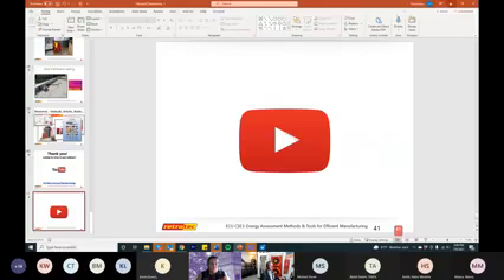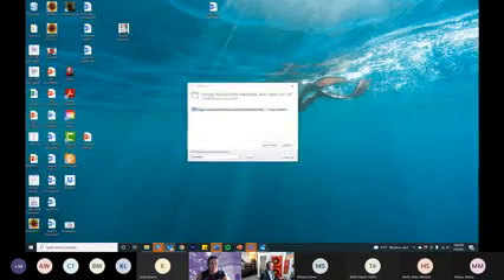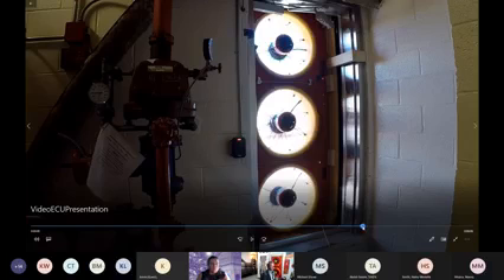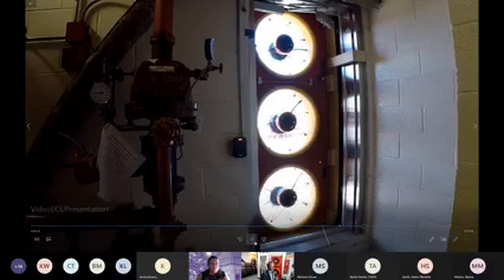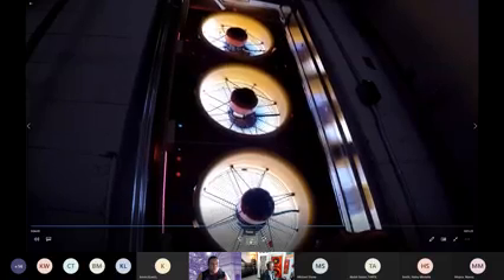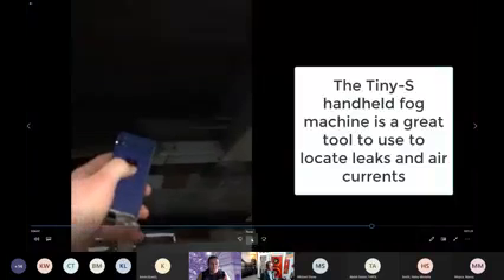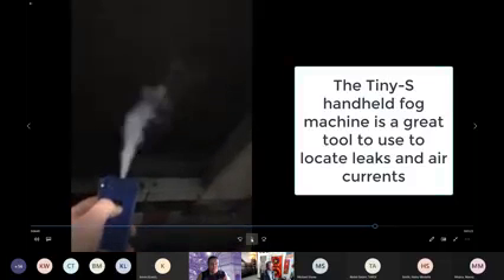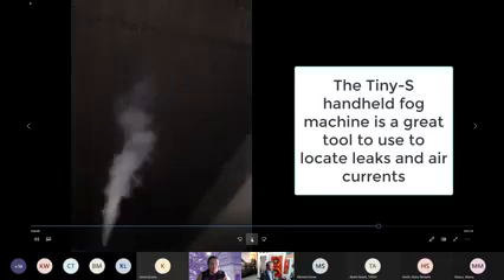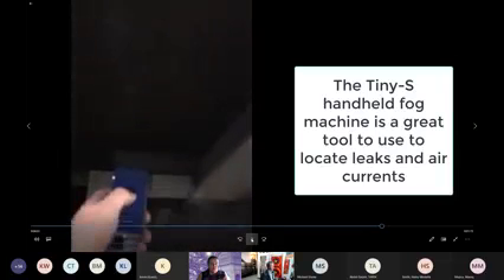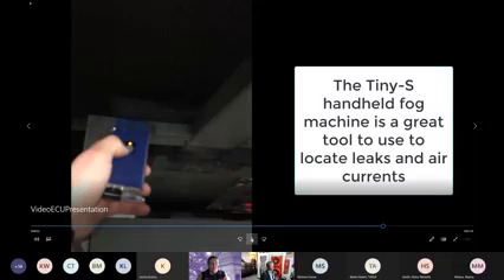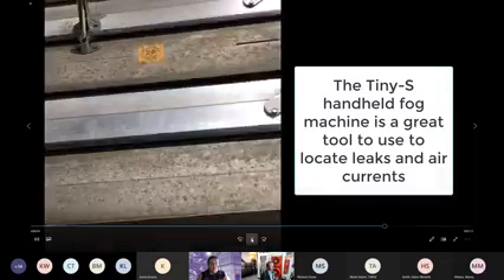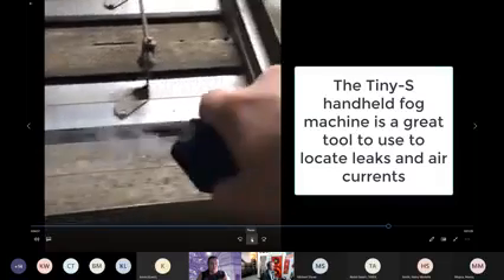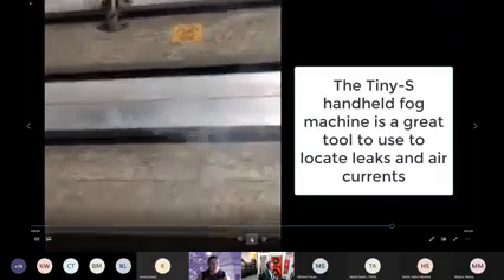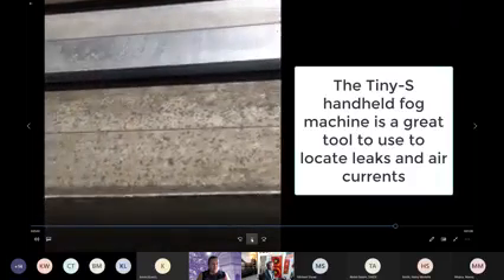And while I still have just a couple of minutes left here, one thing that I'll show you is just what some of this looks like. If we're running fans, this was in an actual building in New York City where we used about 33 of these fans. They were having energy problems and really couldn't afford the utility bills out of their budget. And so we went and tested it. And so using that fog machine, we can see where a lot of these leaks were occurring. At the top of the building, there were all of these louvers up there in the elevator penthouse that were rusted open and didn't have seals, and we could see that smoke escaping through there.